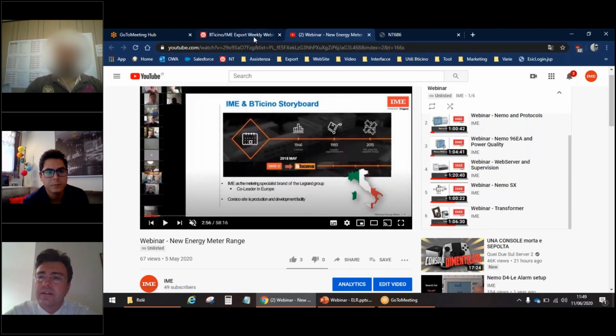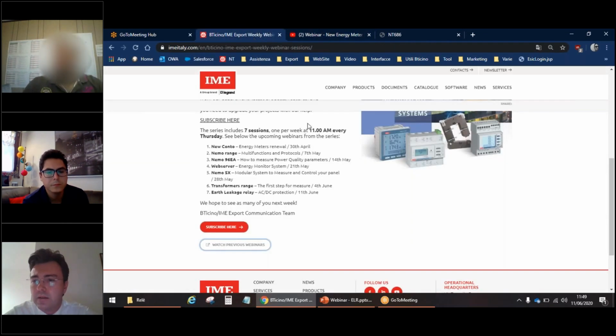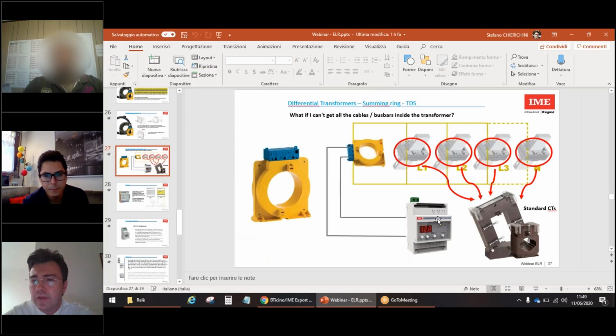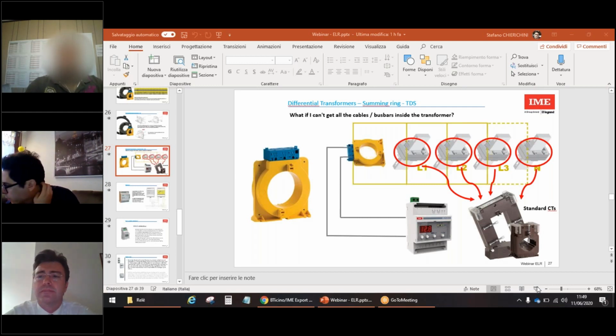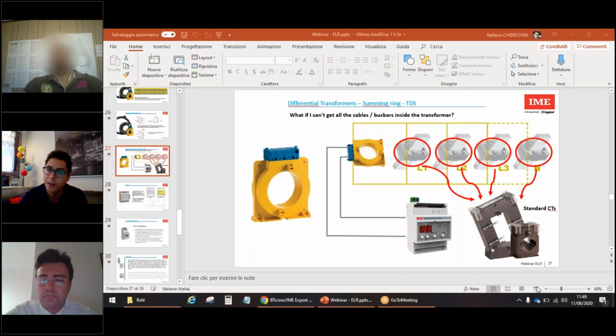For higher ratings like 2000 ampere, what kind of earth leakage relay and toroid can we use? You can use a normal earth leakage relay, but if you have 2000 amps, normally you use a bus bar, so you have to use summing rings. For every single bus bar, you connect a normal current transformer that embraces every single line plus neutral, if you have a neutral, connected in parallel to the summing transformer. This summing transformer works like a normal current transformer toroid and is connected to the ELR.